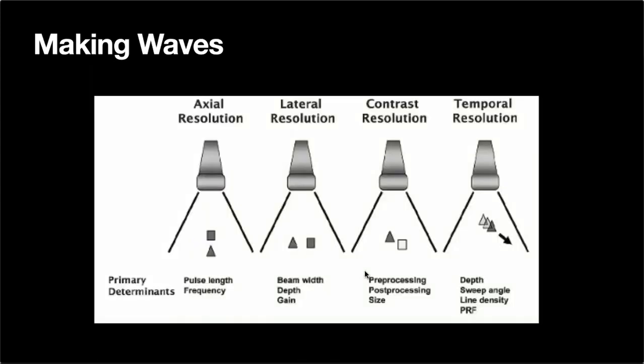To summarize what determines these resolutions: axial resolution is governed by pulse length and frequency. Lateral resolution is dictated by the beam width — fixed by the size of the transducer and how much the phased array can look around — as well as depth and gain. There are also contrast and temporal resolution aspects, which are also important.